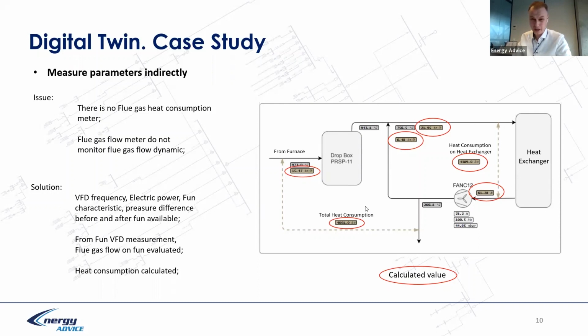So the digital twin allows us to analyze indirectly, for example, the flue gas flow from the furnace. It's a case study, and in fact no additional flow meters are required. And we found that this flow meter, which is installed here on the lower temperature side at 260 degrees, is quite a special flow meter at these high temperatures. The calibration was done badly. That's it. So everything was fixed.